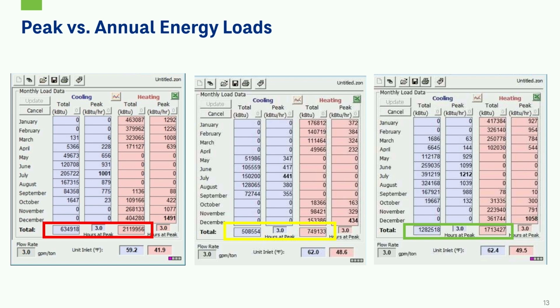So we looked at these three scenarios to stress the importance of your peak loads. They can tell you something. They're helpful for designing your loads and making sure your equipment can serve those peak loads in the building. But you also need to consider, for your ground thermal heat exchanger design, what those balances are annually, and they might not line up with what your peak loads are telling you.